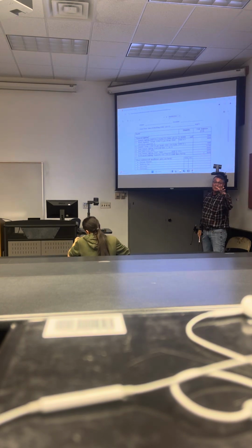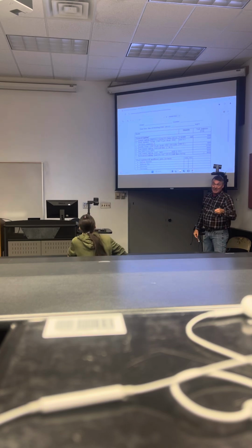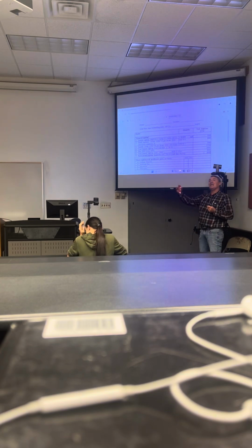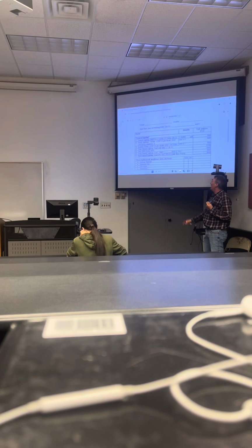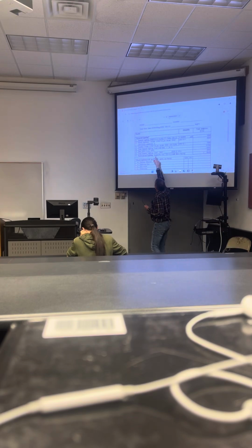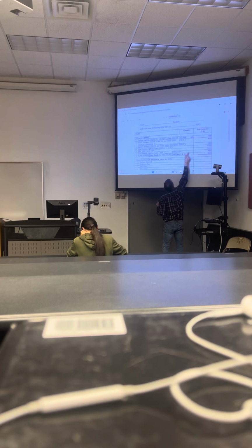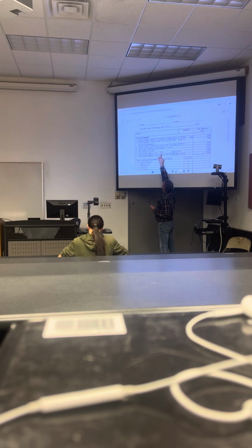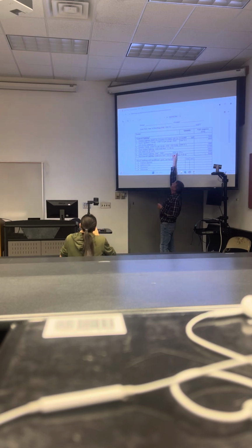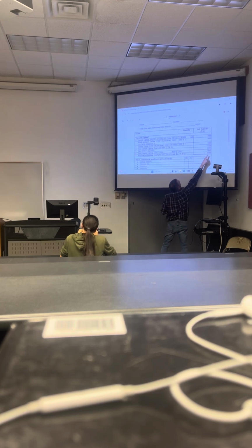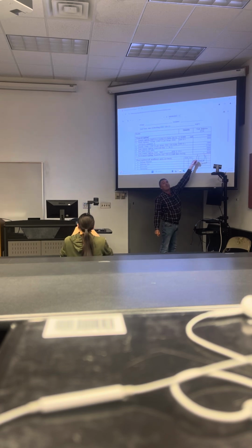First 3,000 is at 100%. So they want you to size 3,000 watts at 100%. Anything beyond that is only 35%. And that's what this line does. So the first 3,000 is 3,000, and then for the remainder, you take your total general lighting load, subtract 3,000, which is 8,700, multiply by 0.35, and that comes out to 3,045. So you take the first 3,000, add it to the 35%, that comes to 6,045.